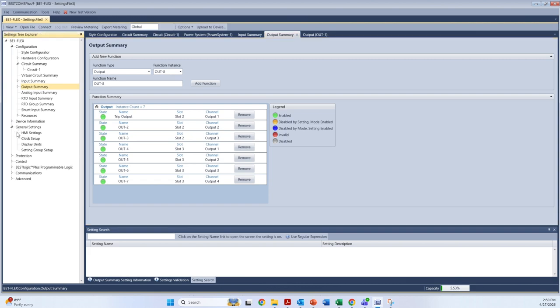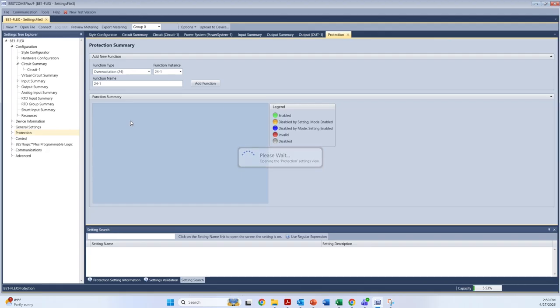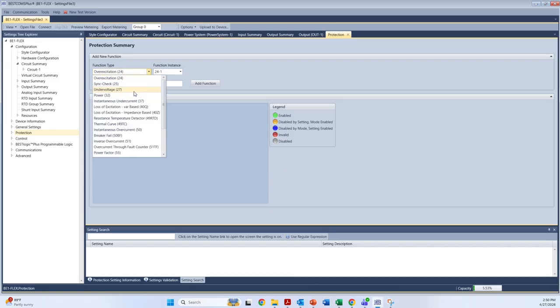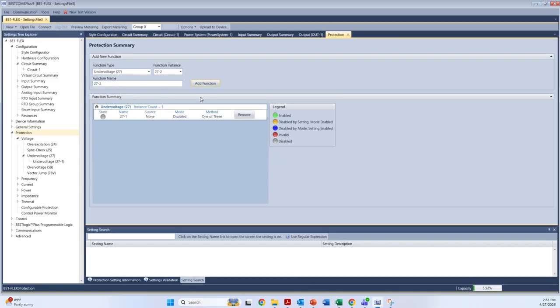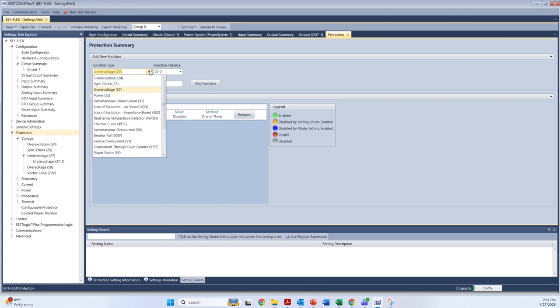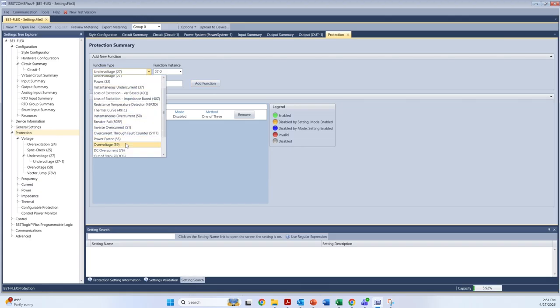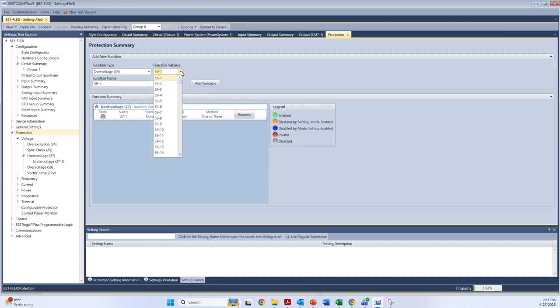For the general device information, you can put in a label and give it an HMI file that you can use on the home screen. We will do some protection elements, a typical undervoltage. We'll do an overvoltage. Notice you have 255 of each of the elements available. So there are a lot of elements available to be used on the relay.